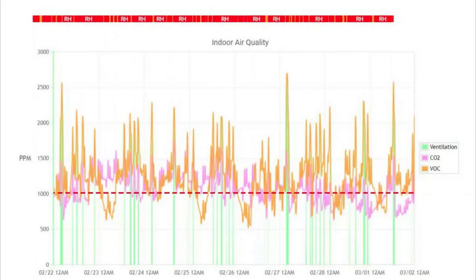And here is home G over the span of 1 week. Clearly, there is a high level of occupant activity triggering the CO2 and VOC sensors. We believe this may be vaping in the home. It's impressive to see how well the demand control system works to keep up with this high level of pollutant generation. While the levels do exceed the OSHA limit, the system regularly works to keep the home from getting to potentially dangerous levels. Imagine how this home would look without this level of demand ventilation.